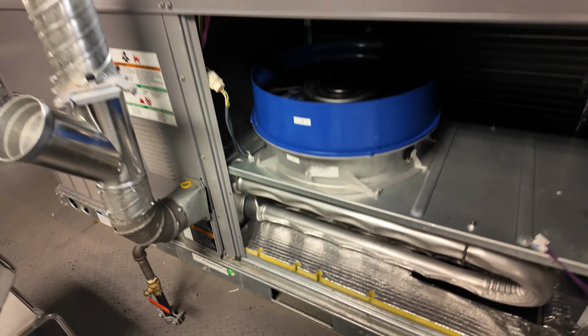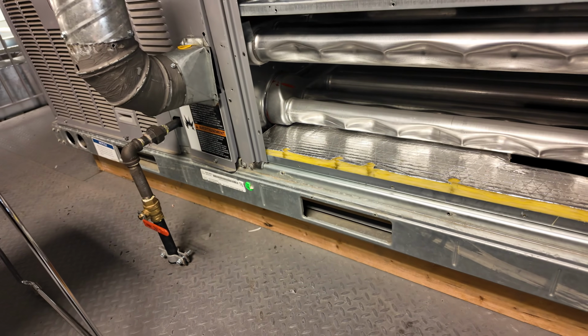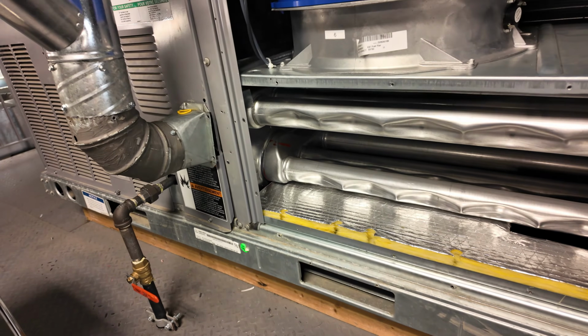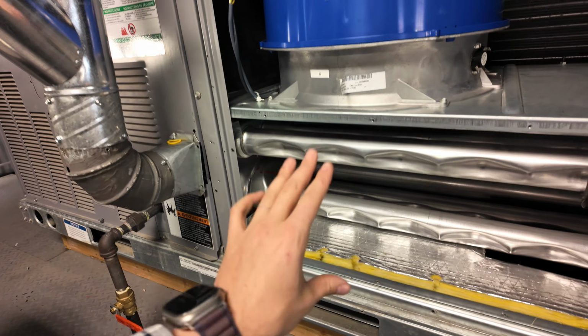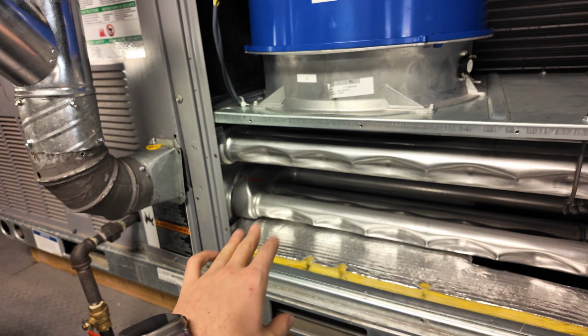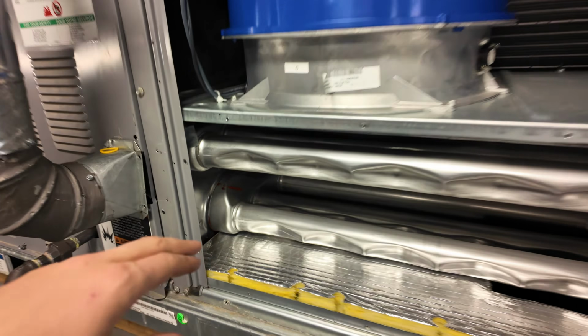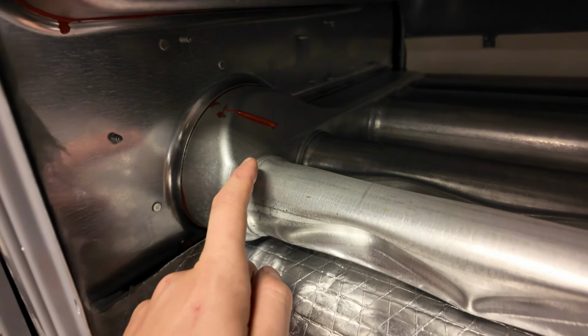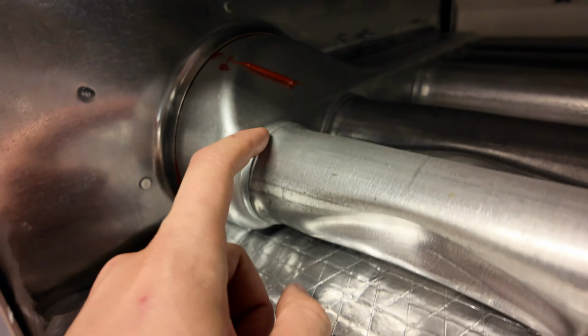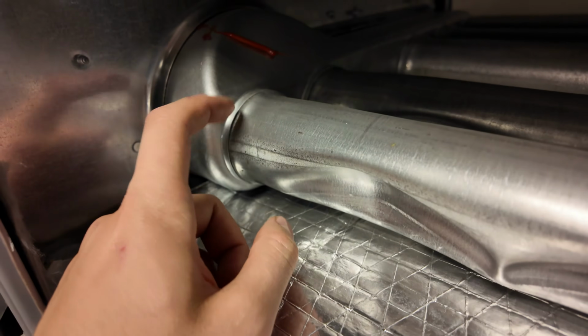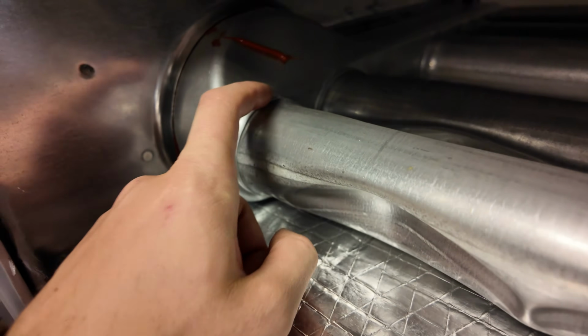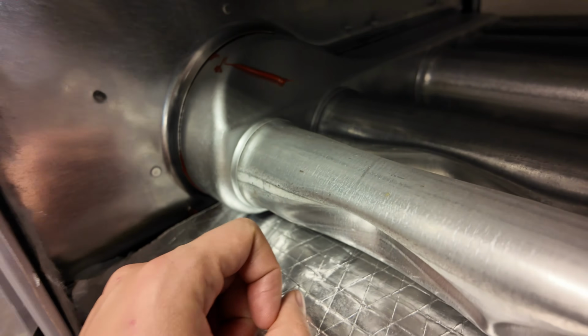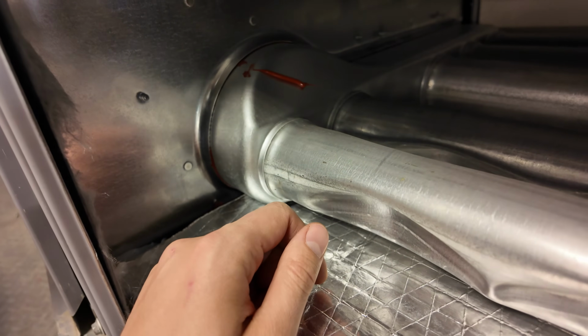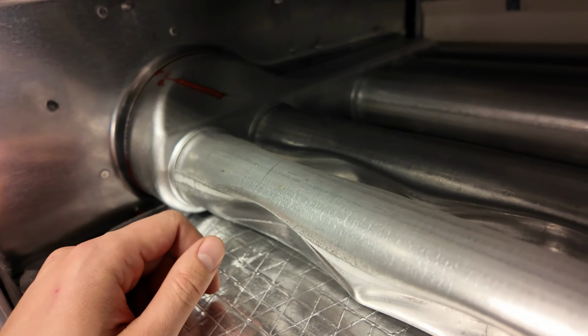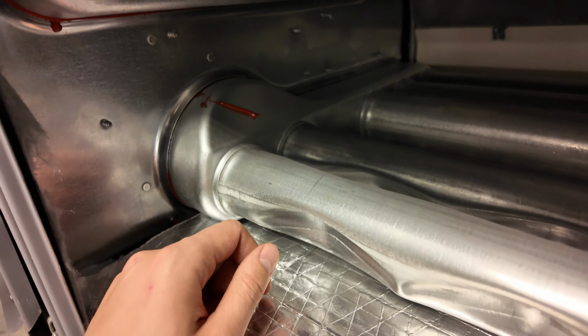As you guys probably are aware, Carrier are notorious for cracking in the same spot. I've seen heat exchangers that are 2 months old and they crack in this exact spot all the time. So if you come down here, there's this seam right here. Usually on the top side, sometimes the bottom side, this seam right here will crack. I've seen cracks 2 months old on a unit. Really depends kind of how they're set up for airflow.